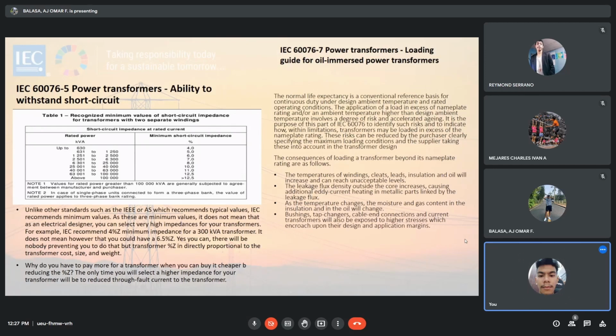These risks can be reduced by the purchaser clearly specifying the maximum loading conditions and the supplier taking this into account in the transformer design. The consequences of loading a transformer beyond its nameplate, pag sumobra siya sa nameplate rating ng isang transformer. So, the temperature of winding leads, insulation and oil will increase and can reach unacceptable levels. The leakage flux density outside the core increases, causing additional eddy current heating in metallic parts linked by the leakage flux. As the temperature changes, the moisture and gas content in the insulation and in the oil will change. Bushings, tap changers, cable and connections, and current transformers will also be exposed to higher stress which encroach upon their design and application margins. Next.